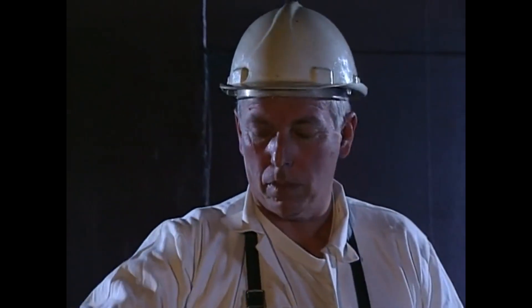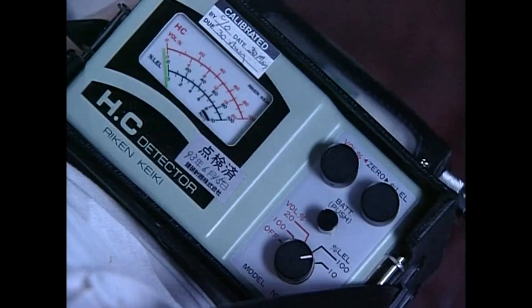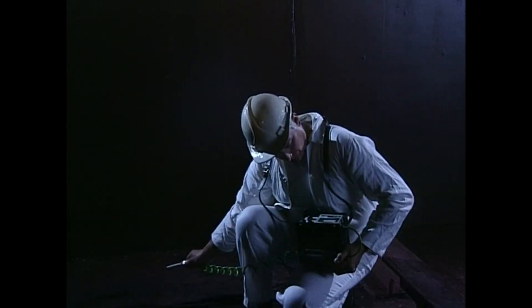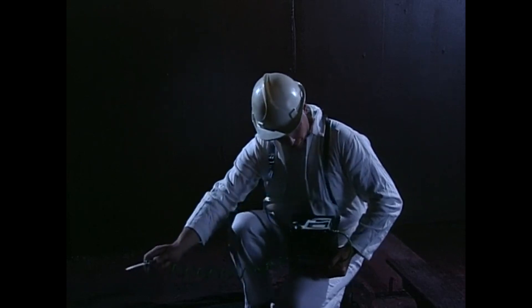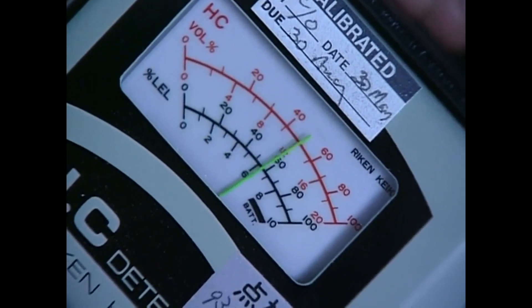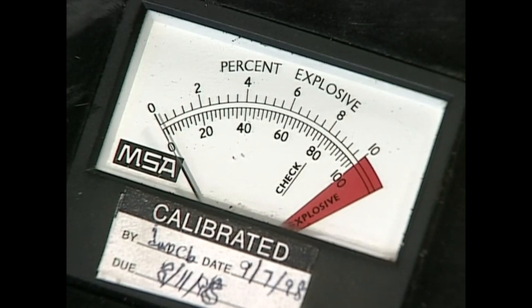Among the most common types of flammable gas detectors are catalytic instruments. The catalytic process involves burning minute quantities of gas, but beware — because they work in that way, if there's less than 13% oxygen in the atmosphere, catalytic detectors won't work properly. Over time, your detector may stop working correctly if it isn't properly maintained, yet it may still look as if it is working and that no gas is present. Also, many detectors of this type — particularly the older and simpler models — show a reading above the LFL, that's to say probably within the flammable range, the danger area, with one strong deflection, after which it usually drops to near zero. So if you're not paying attention, you could miss the danger signs.